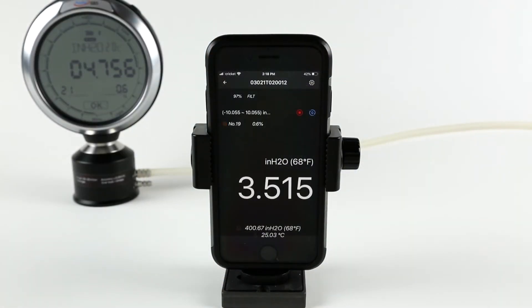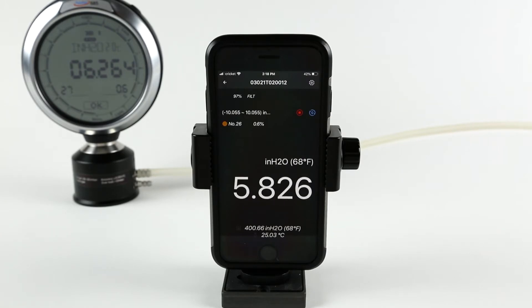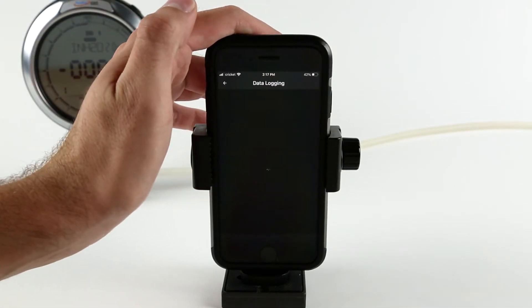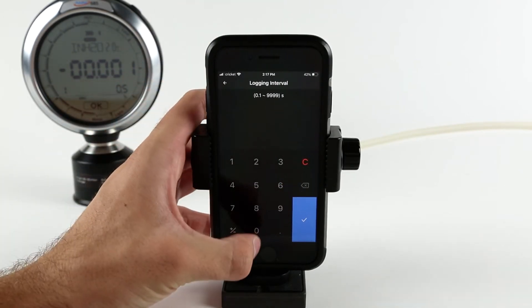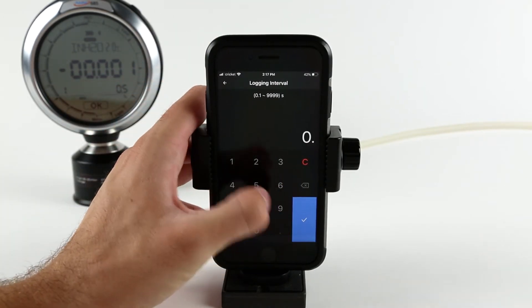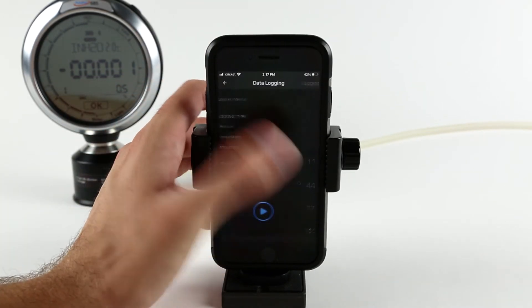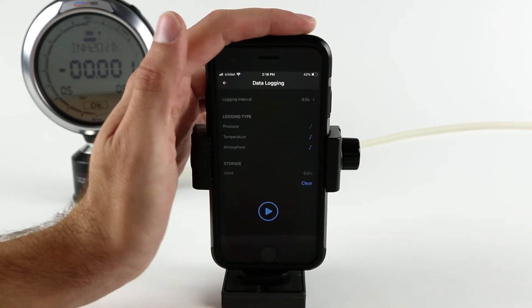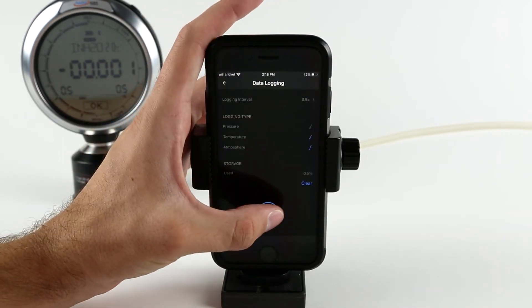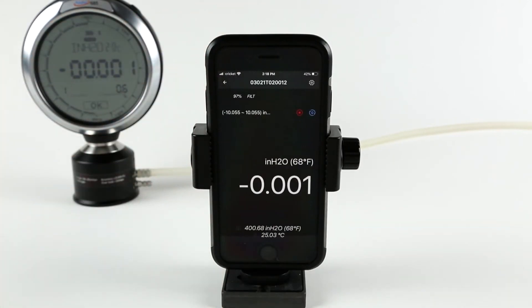Additel Link makes starting and stopping a log session extremely easy. Simply select the record icon to go to the data logging menu and set the logging selections. Logging intervals can be set at a tenth of a second to once every 9999 seconds. Pressure is automatically recorded with the date and time.